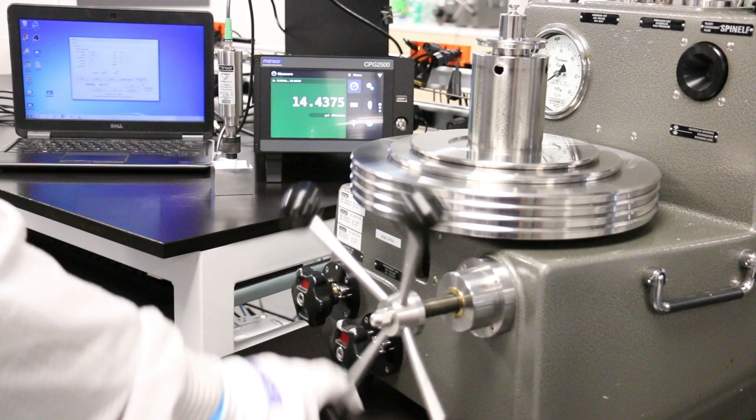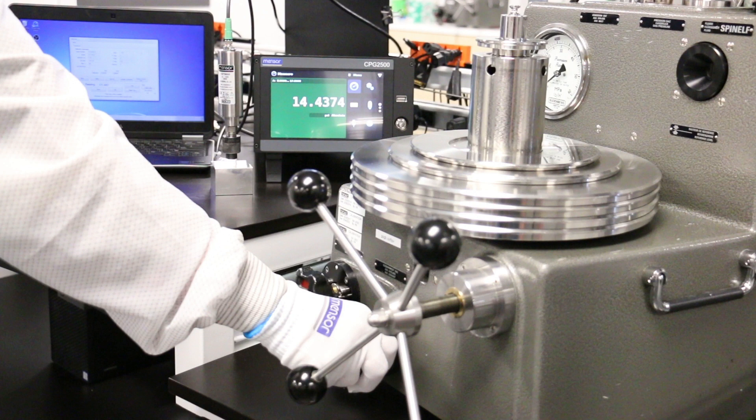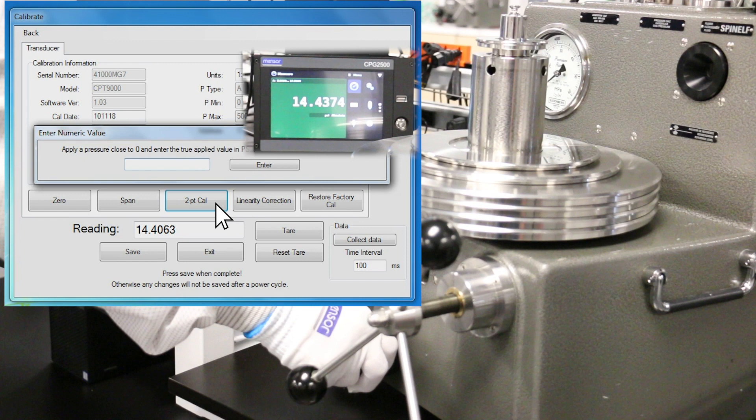Begin the calibration with the pressure vented to atmospheric pressure. When a stable zero point is reached, compare the reading with the precision barometer. Record both values if as-found data is needed. Click the two-point calibration button on the utility software and enter the value from the barometer.